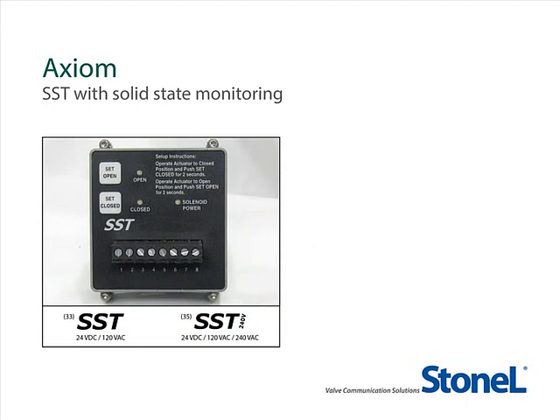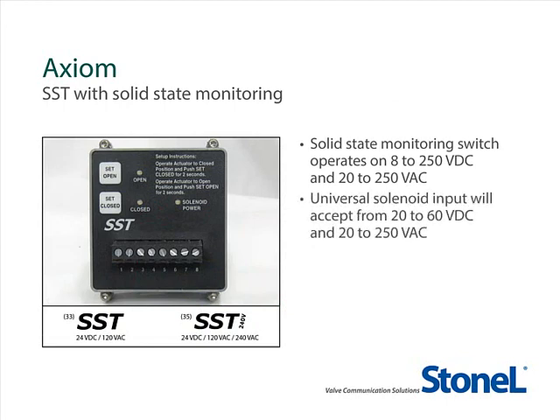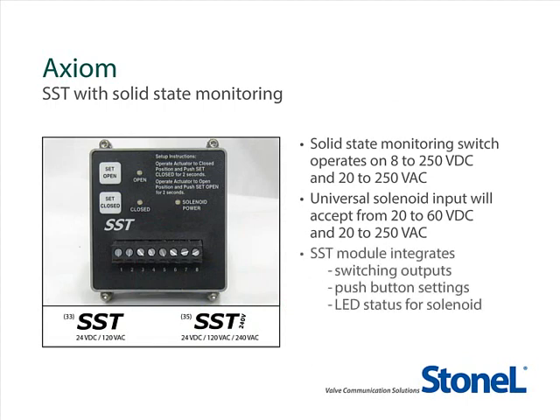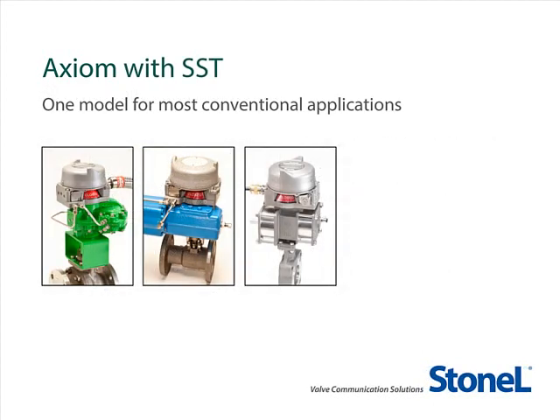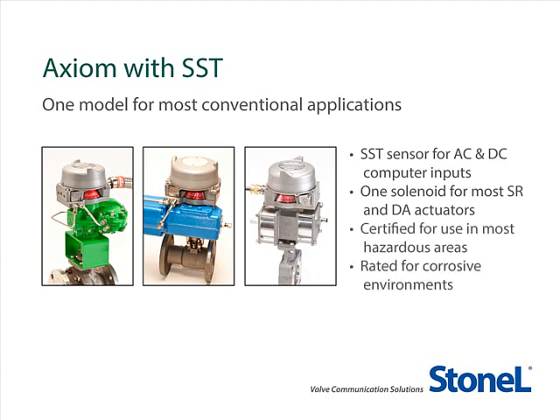The Axiom with SST switches is capable of operating from 20 to 250 volts AC and 8 to 250 volts DC monitoring circuits. The solenoid input is also capable of operating from 20 to 60 volts DC and from 20 to 250 volts AC. The SST module integrates solid-state switches and solenoid voltage conditioning, all with LED indication, open and closed push-button settings, and a high-accuracy magnetic sensor system. With the same AX model, you can have spring return or double-acting actuators, AC or DC monitoring applications, AC or DC outputs driving the solenoid valve, and hazardous corrosive environments. By stocking just one model in your plant, you will be able to satisfy a number of different applications.